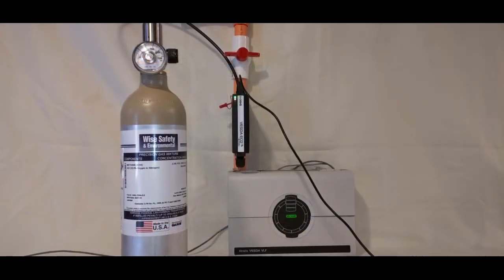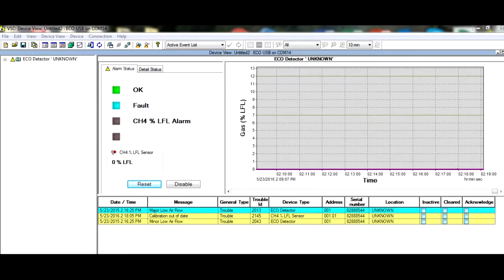Now switch the regulator to the span gas cylinder. In our case, we're using methane at a 50% LFL concentration. At this point, we would bump test the detector before we span calibrate. Open the regulator and allow the gas to flow.